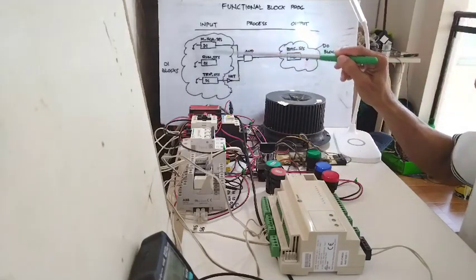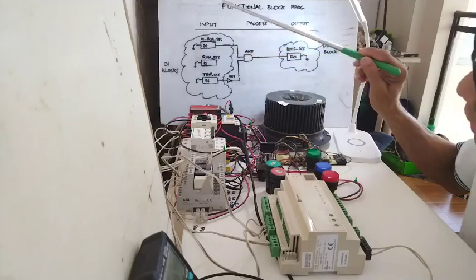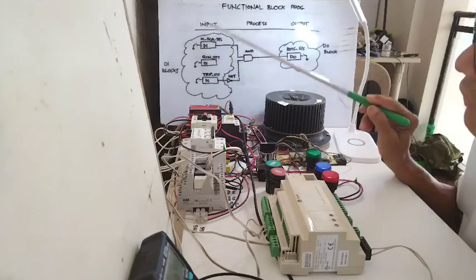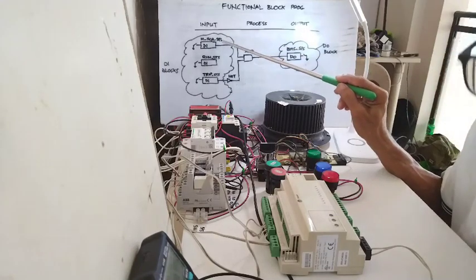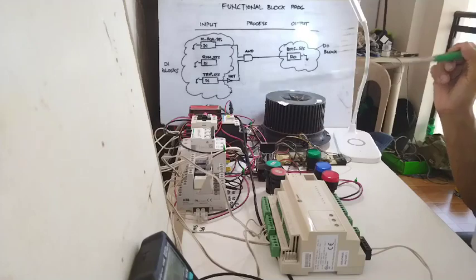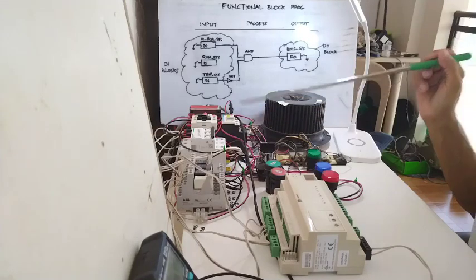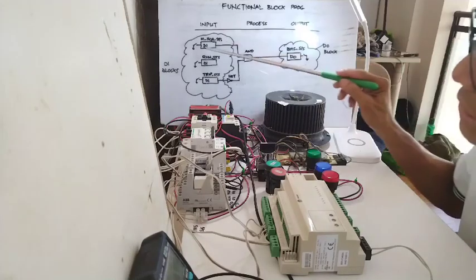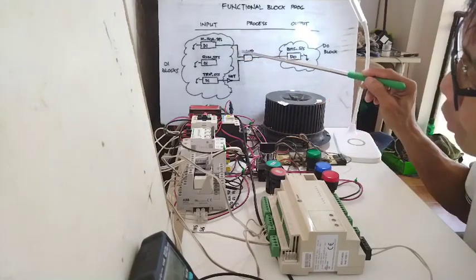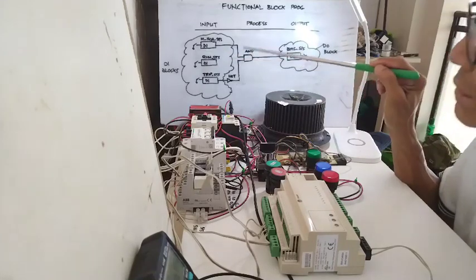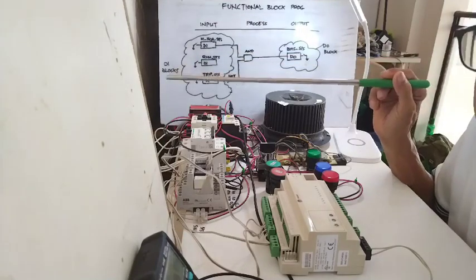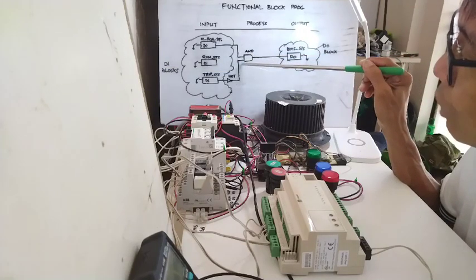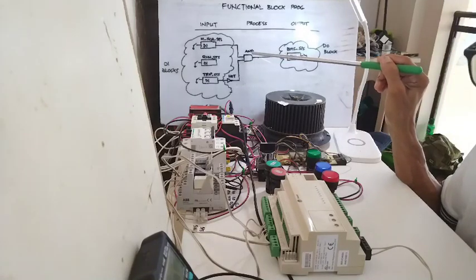I have defined my three digital inputs. Now, in order to start the control panel, I need two pieces of information. First, I need to know if the panel is in auto position — if the selector switch is already in auto. When someone puts the selector switch in auto, this contact will close and this input will become 1, giving input A of the AND gate a value of 1. The AND gate truth table requires both inputs to be 1 before the output will be 1.